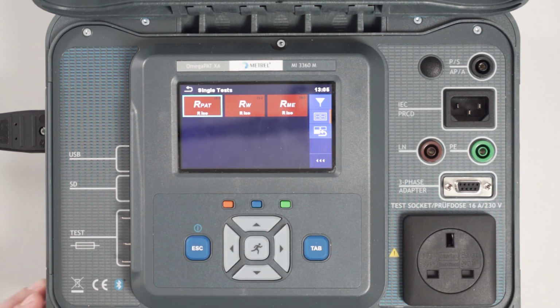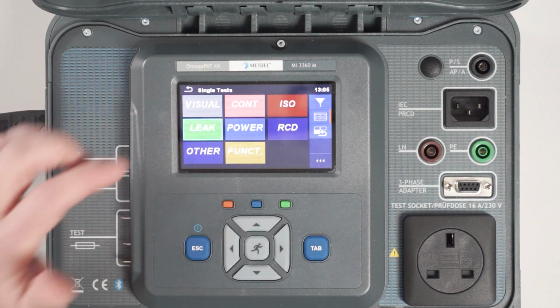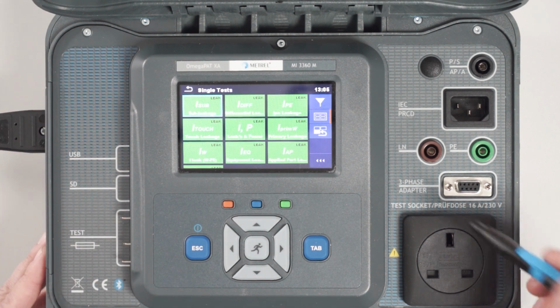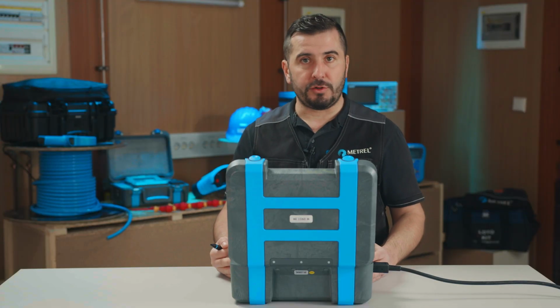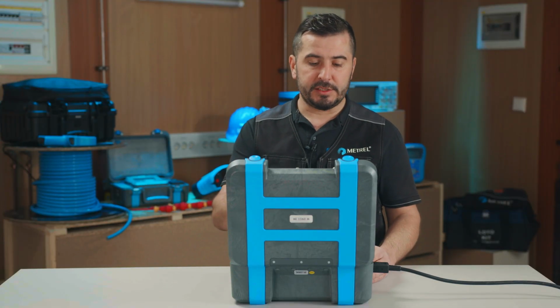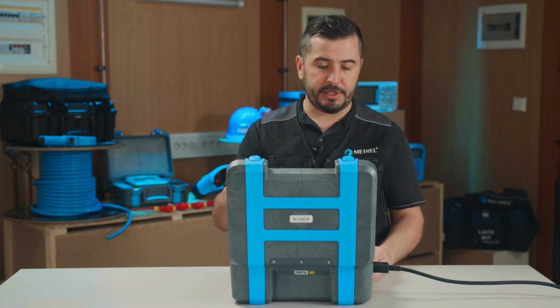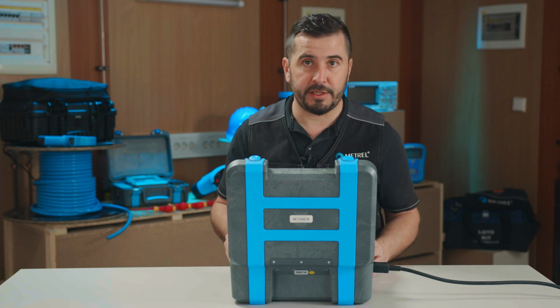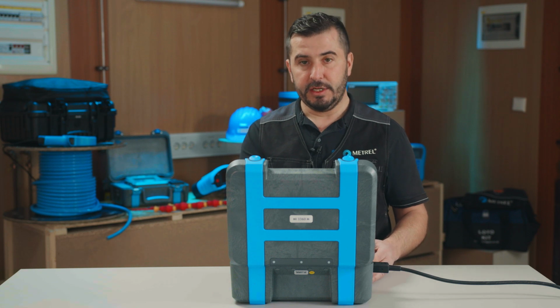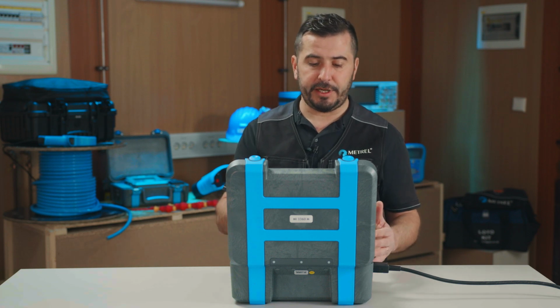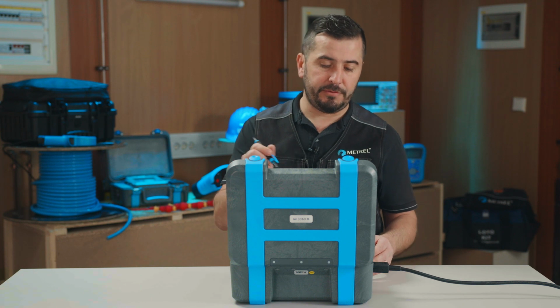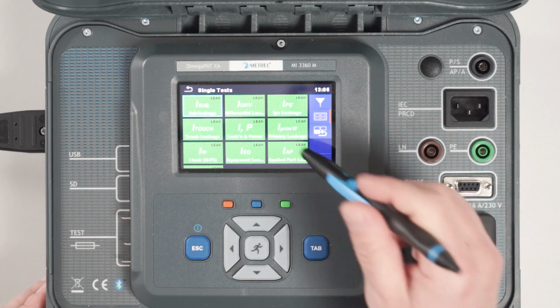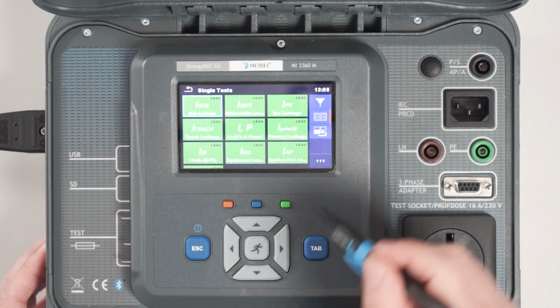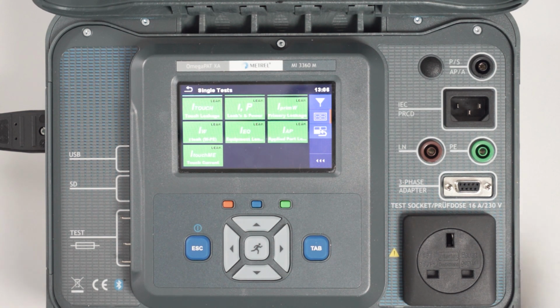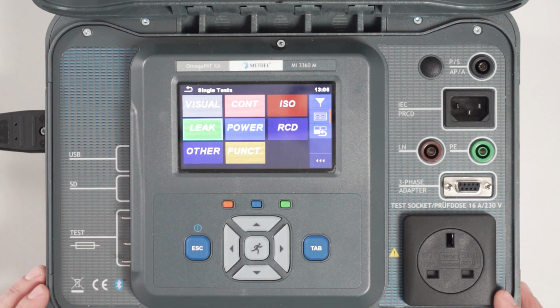The measuring principle is the same. Under leakages, we have several different options for leakage current measurements. Resolution is in microamps due to the fact that the instrument is designed also for medical appliance testing. So we have substitute leakage measurement, differential, P, touch leakage, we have leaks and power, we have primary leakage for welding, normal leakage for welding, equipment leakage, applied part leakage and touch leakage for medical appliance testing.